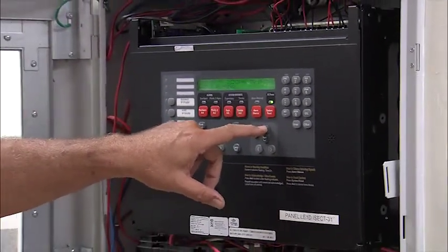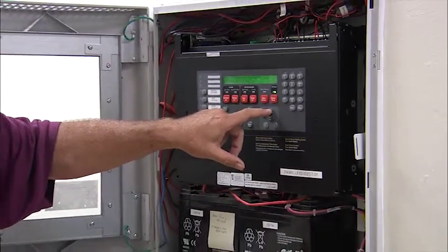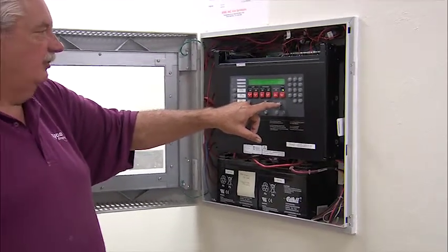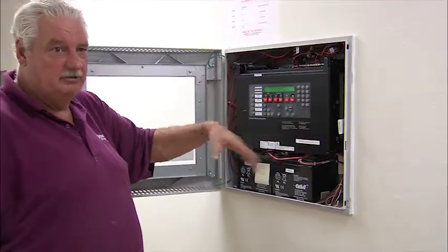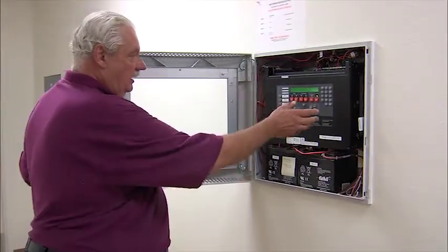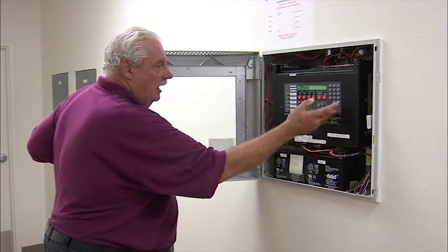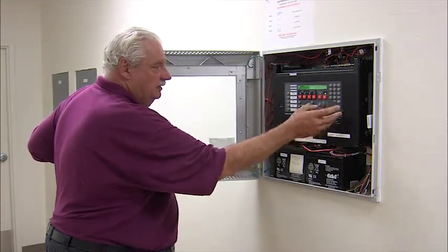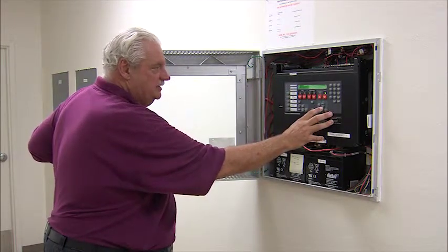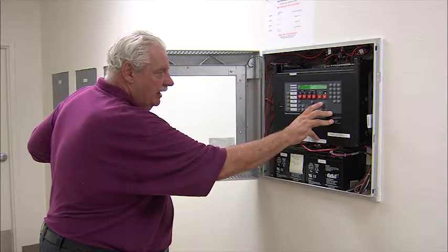It'll probably list extender power supply battery trouble, and so forth. So you can actually go in and check the history if somebody says it's beeping but it wasn't. And before I leave, I'll clear that so there's nothing in there currently. Same thing for the alarms. I don't know if they're still in there. Fire alarm, 11:46 Saturday, 3:19 a.m.